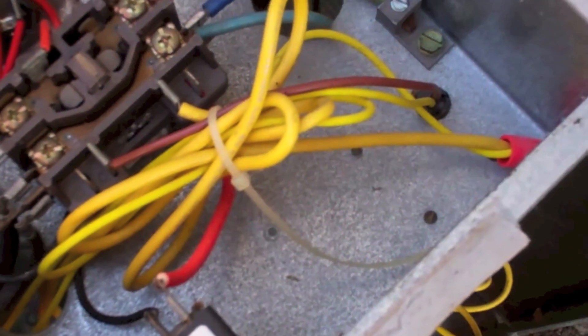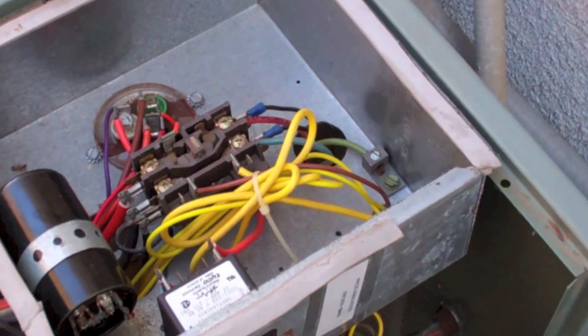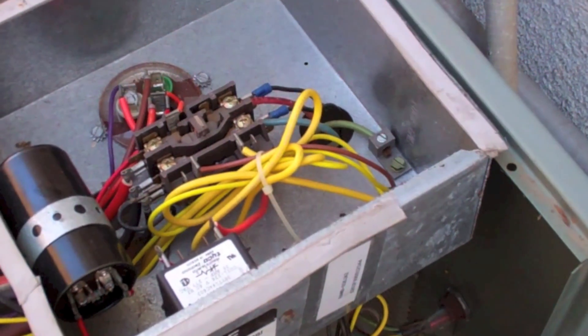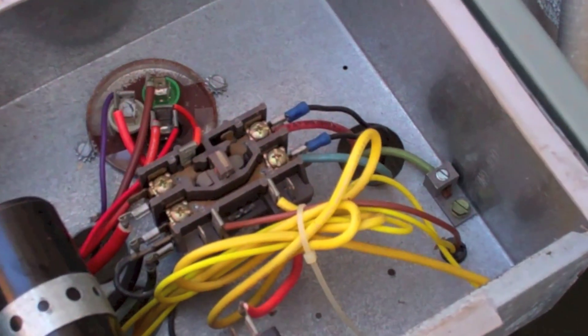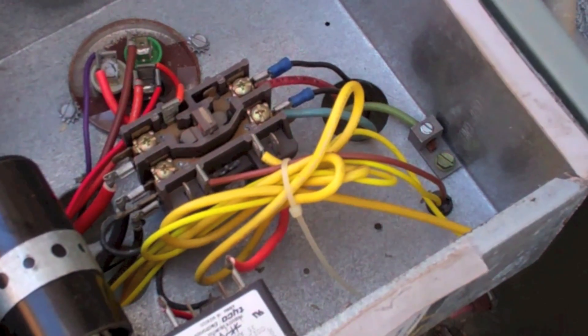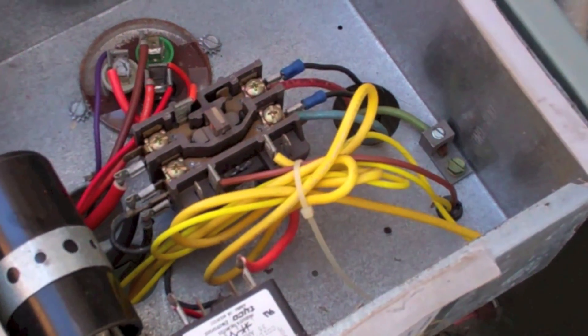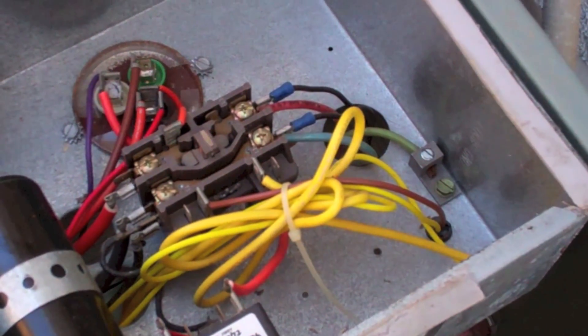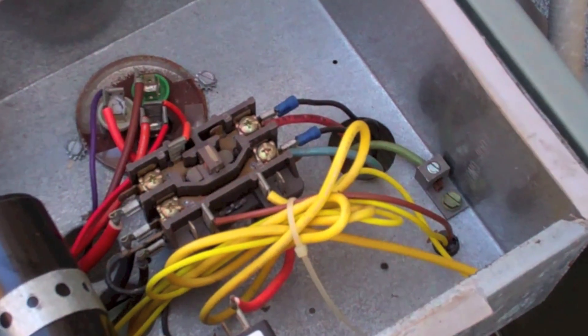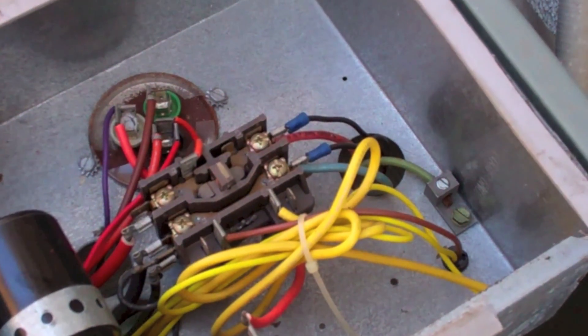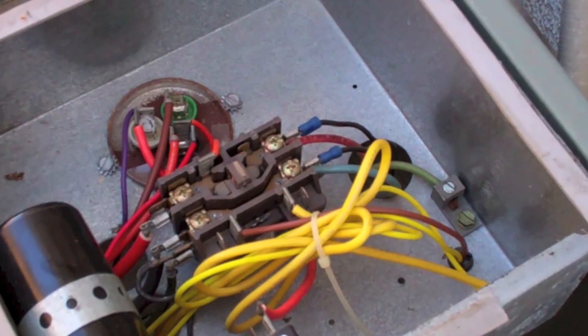So the base is going to go there, it's going to mount on the top. It's going to be pretty easy. The neighborhood that it's in has experienced low voltage in the past, so the contacts are pitted. It's not uncommon to see the voltage down to 217. So with the optical sensor, I don't have to worry about my contacts going to mush anymore. It's gonna be pretty easy.